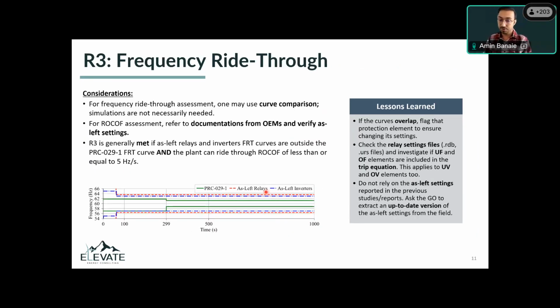For requirement R3, frequency ride-through, we do a curve comparison. Unlike the voltage, this is a universal parameter, so you can put all these FRT curves on the same figure, and if the as-left settings of the relays and inverters are outside the PRC-029 curve, then that shows compliance with the FRT side of R3. One point that I've seen a lot and I want to highlight here is the case where 2 curves overlap, like something as you see here. Different approaches can be taken here. Some may say the as-left settings of the inverters in this case is not going to operate for this 57 hertz, and it's set to like 56.99. It's like less than, and it's not less than or equal.